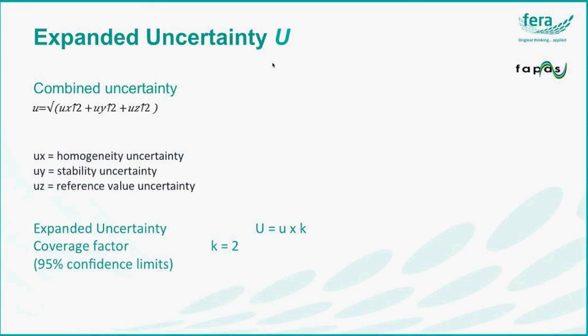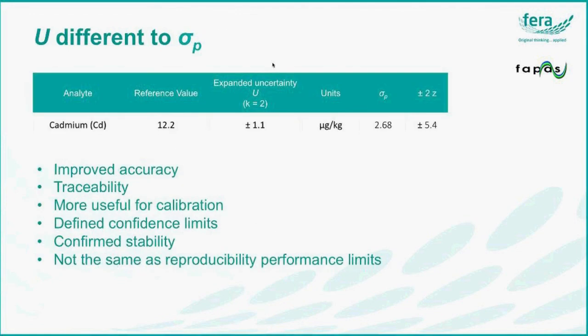For simplicity, the coverage factor equals 2, so the expanded uncertainty is the uncertainty multiplied by that coverage factor. This is standard practice across the majority of analytical chemistry. You can see in this example that the expanded uncertainty is 1.1, compared to the standard deviation for proficiency of 2.68. That means the uncertainty of the reference value is much closer and with a tighter boundary than the performance limits, which represent the required reproducibility of an analysis.